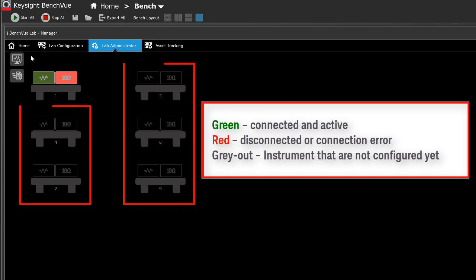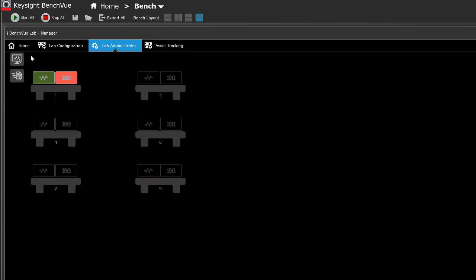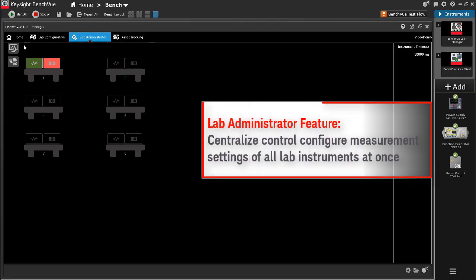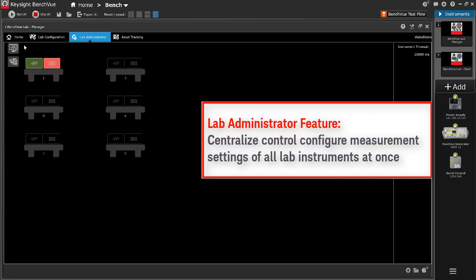Grey out indicates instruments that are not configured yet. Lab Administrator also allows the lecturer to configure the measurement state or settings of all the instruments on the benches in bulk easily. This feature enables centralized control for the lecturer to quickly reset or send a preset measurement state or setting to all the instruments at once for a specific measurement session.